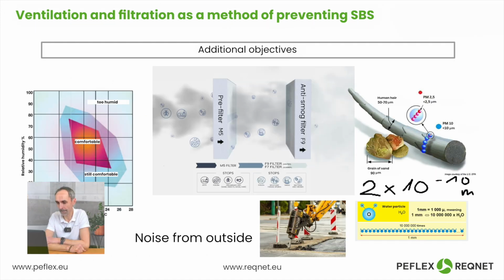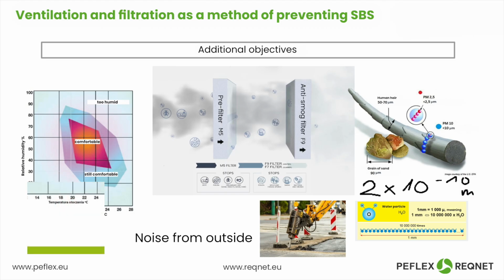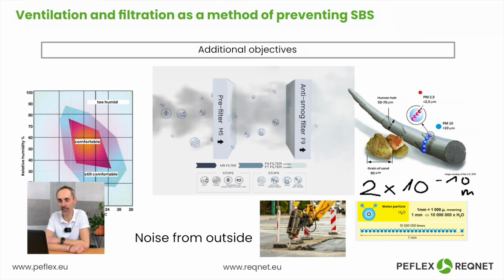The second factor, which is also generated inside buildings, is moisture. When we cook, dry clothes, or do other activities that add water to the air, we can end up with excess moisture, and it's the ventilation system's job to remove that excess. But we also have situations when the air is too dry. This happens in the winter, when the outside air has lower humidity than the air inside the building, so we can end up with what's called overdrying of the air.